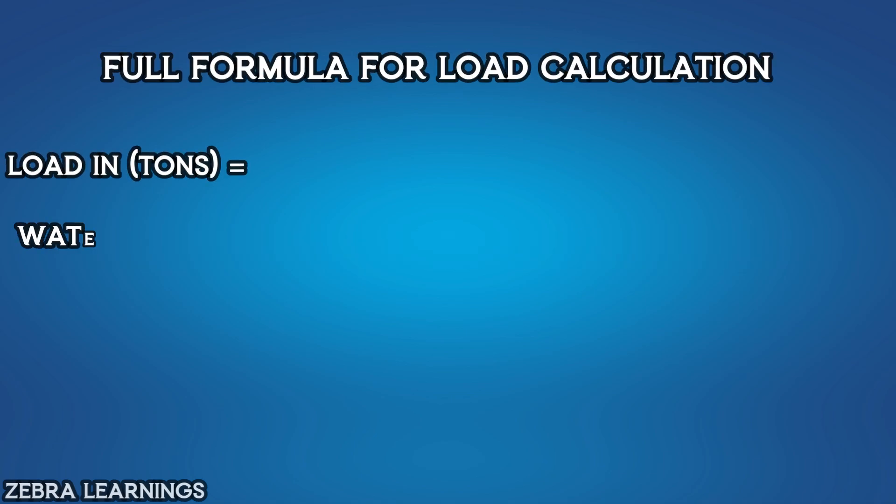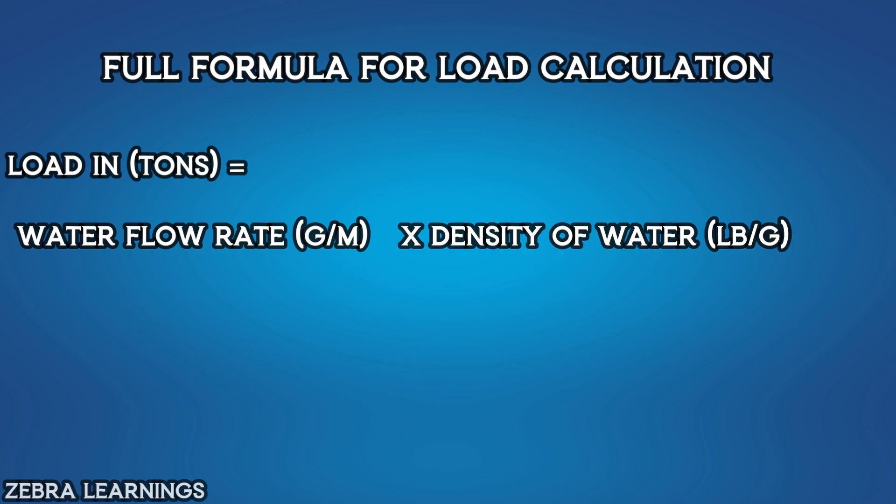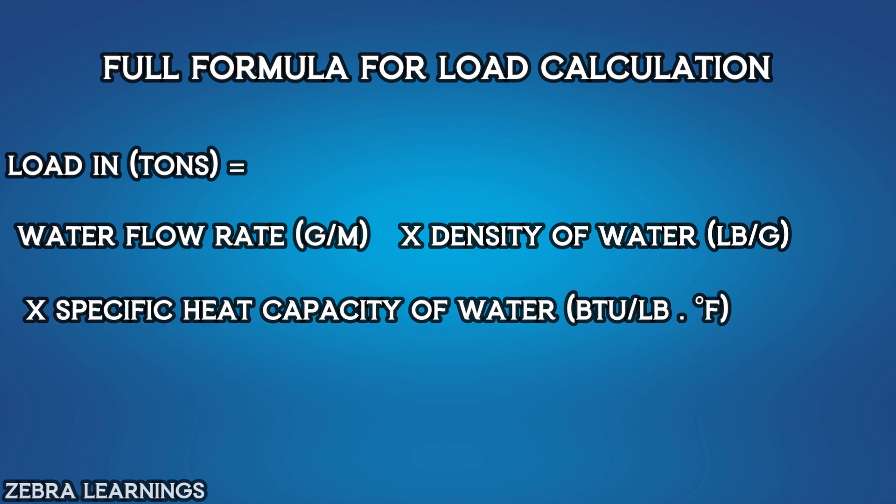Full formula for calculating load. Load in tons is equal to water flow rate in gallons per minute, multiplied by the density of water in pounds per gallon, multiplied by water's specific heat capacity in BTU per pound degree Fahrenheit, multiplied by delta T in degree Fahrenheit. This is the full formula for calculating load.